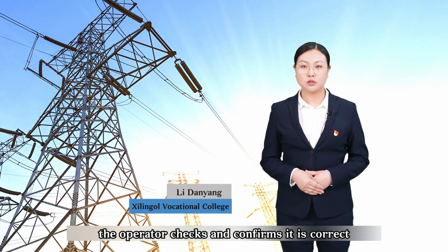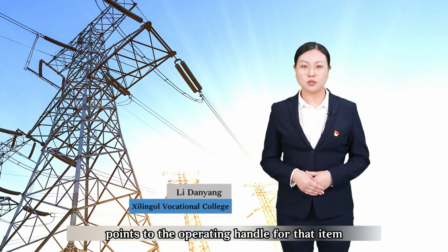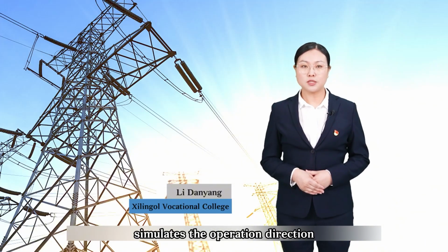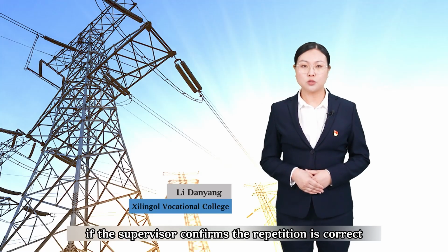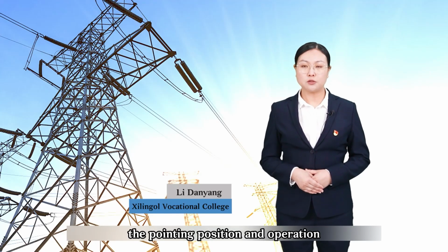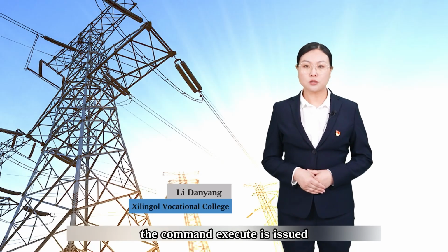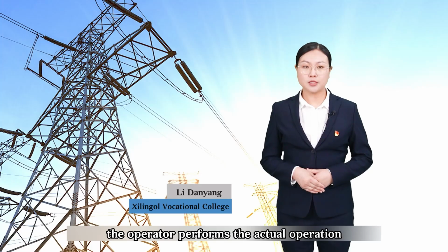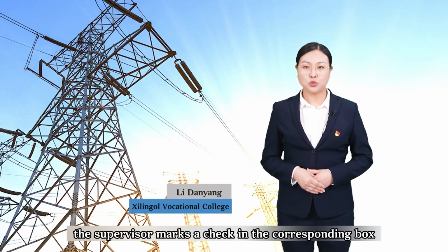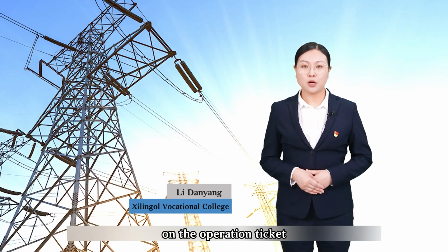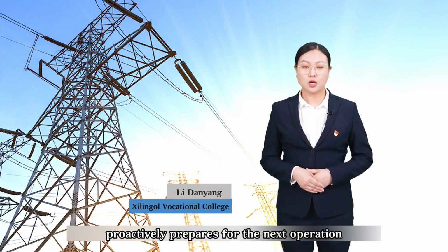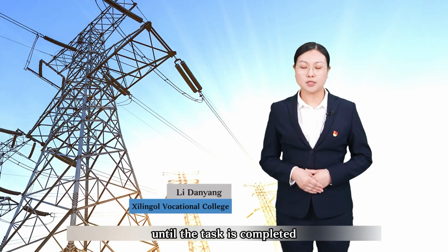While listening, the operator checks and confirms it is correct, points to the operating handle for that item, simulates the operation direction, and loudly repeats the command. If the supervisor confirms the repetition is correct, the pointing position and operation direction are accurate, the command execute is issued. Upon hearing this command, the operator performs the actual operation. After each operation, the supervisor marks a check in the corresponding box on the operation ticket, ensuring it does not exceed the box. After seeing the check mark, the operator proactively prepares for the next operation and then proceeds step by step until the task is completed.